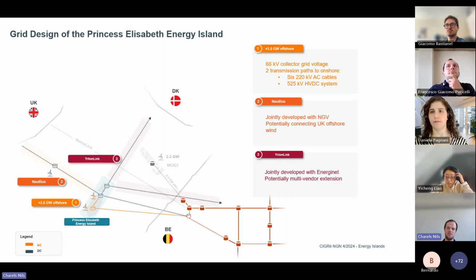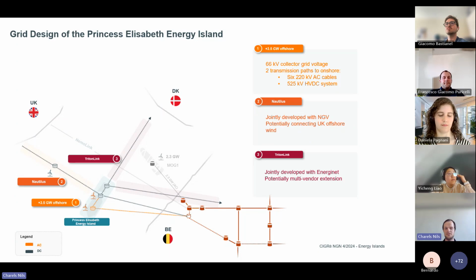In parallel with that, we'll also have a 525 kV HVDC bipole system. The reason we have the HVDC bipole system is that it enables the second driver of providing HVDC interconnections. The first one, being developed jointly with National Grid, is the Nautilus interconnector, which will connect from the DC bus bar on the Princess Elisabeth Island towards the UK, and potentially also connect to an offshore wind farm in UK waters.